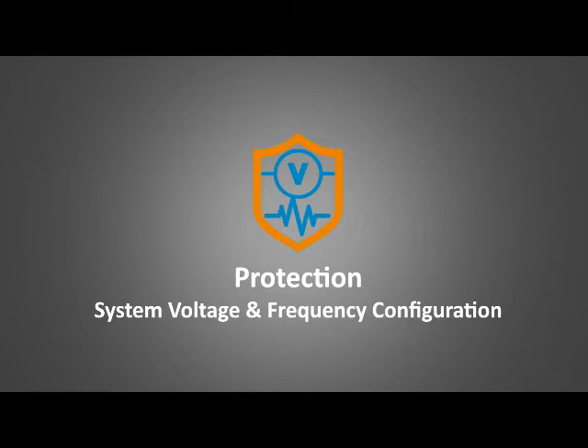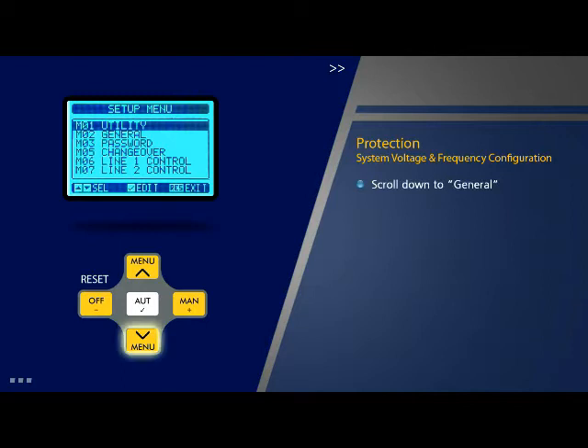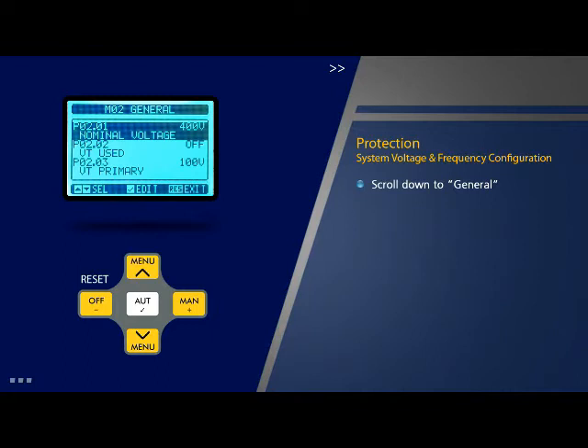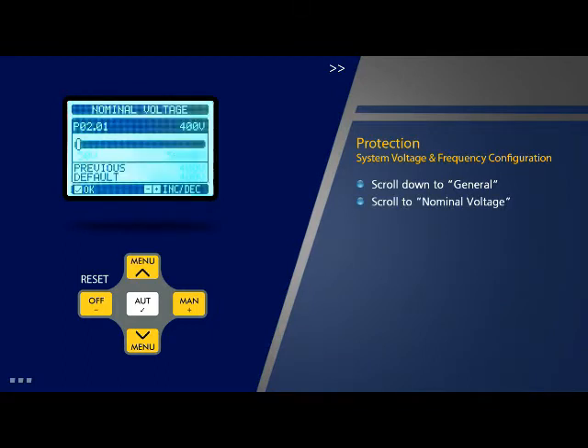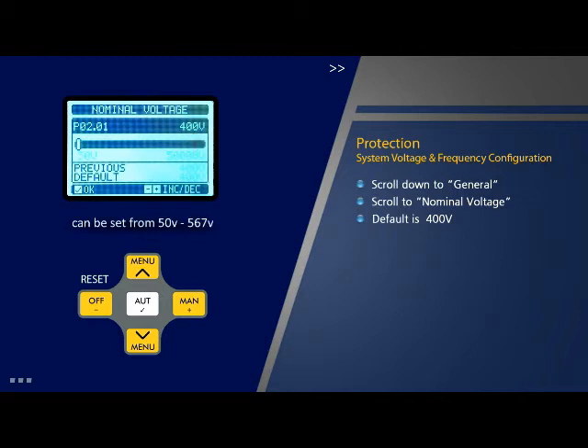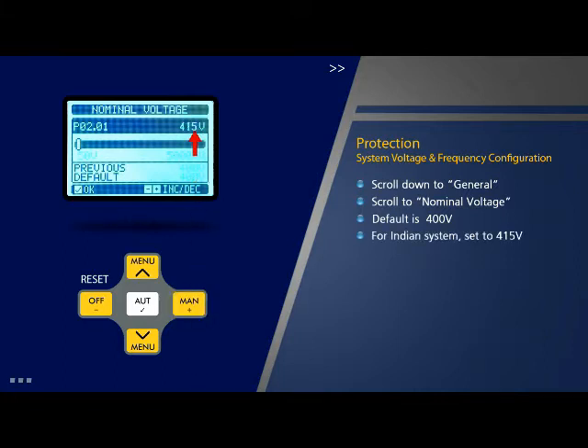Protection — system voltage and frequency configuration: To start, let us look at the procedure for setting the system voltage. Scroll to select the second parameter 'General' from setup menu and press OK. Scroll down to parameter 'Nominal Voltage' on this page. The default value is 400 volts and it can be set to any value between 50 volts and 567 volts. For the Indian system, scroll and set the value to 415 volts and press OK.